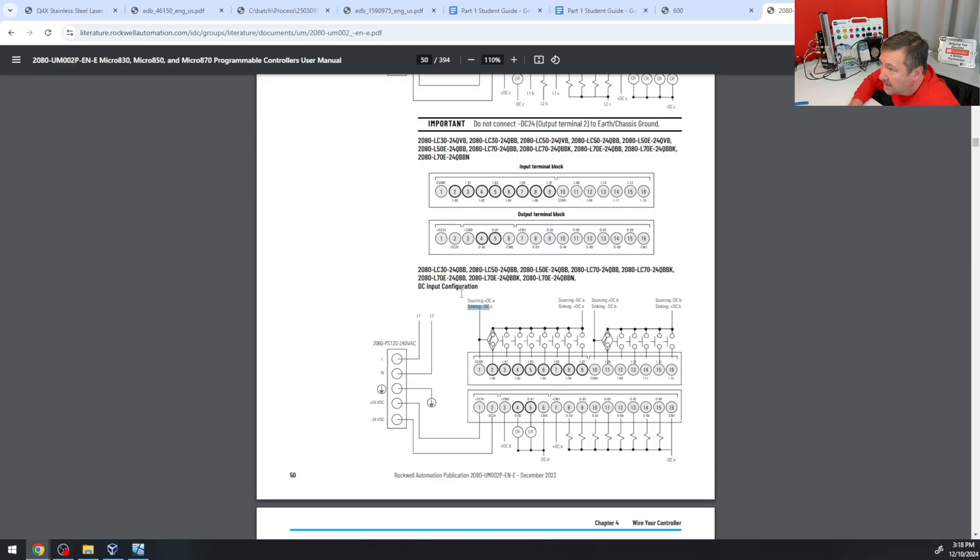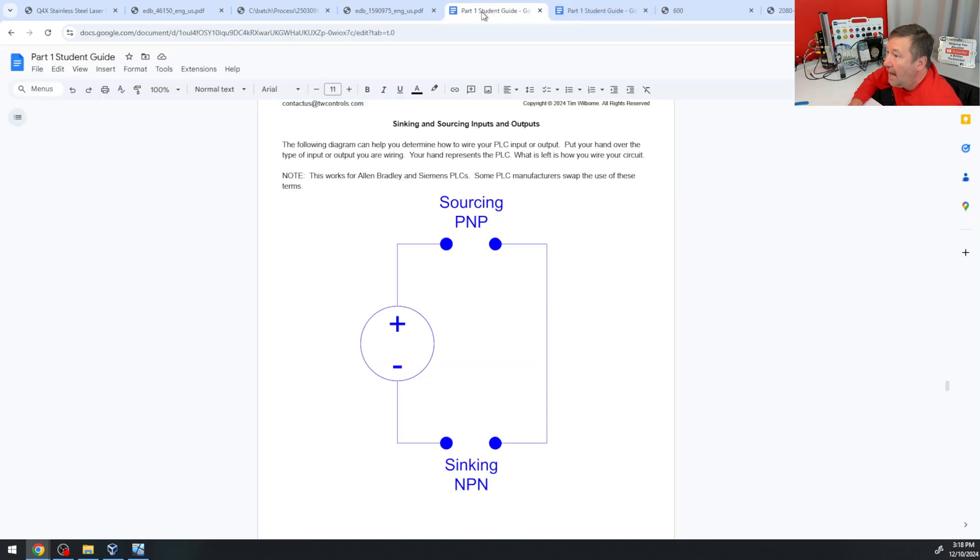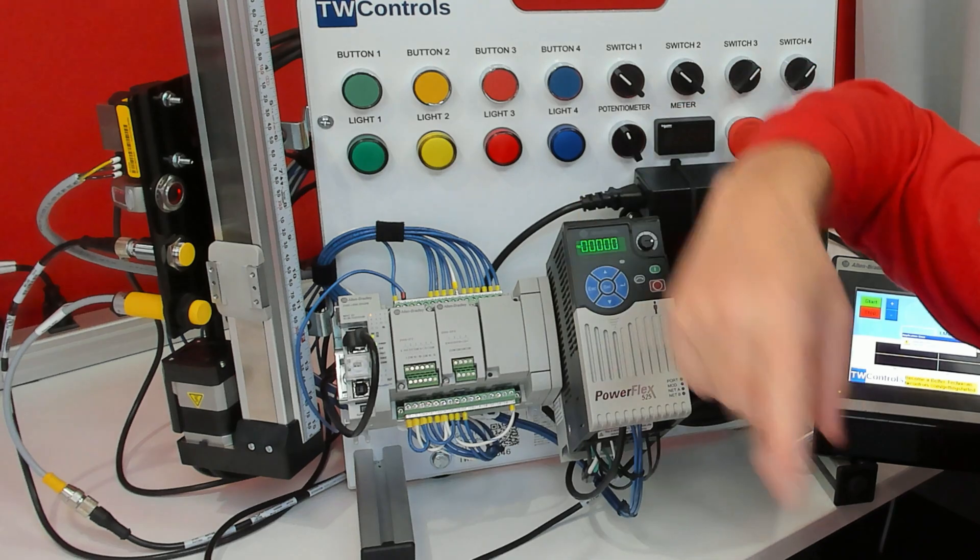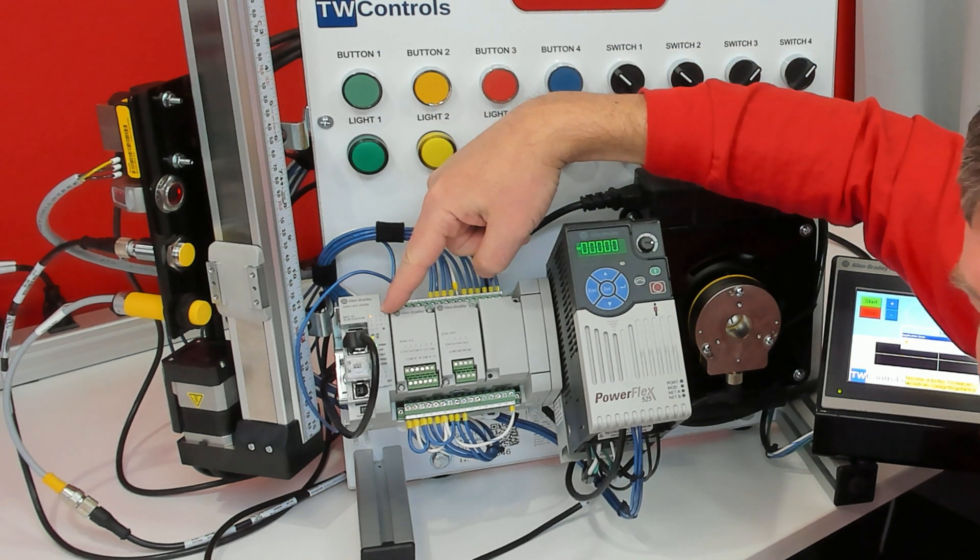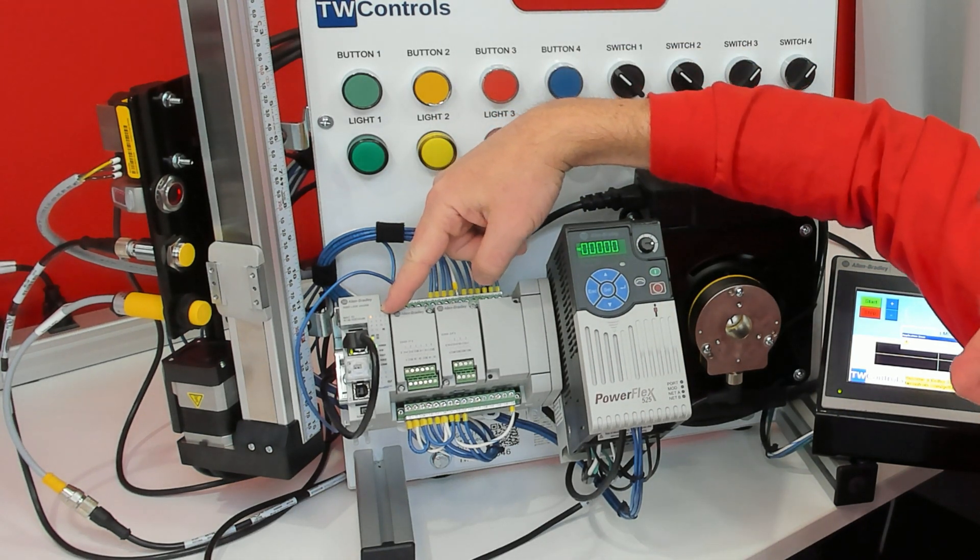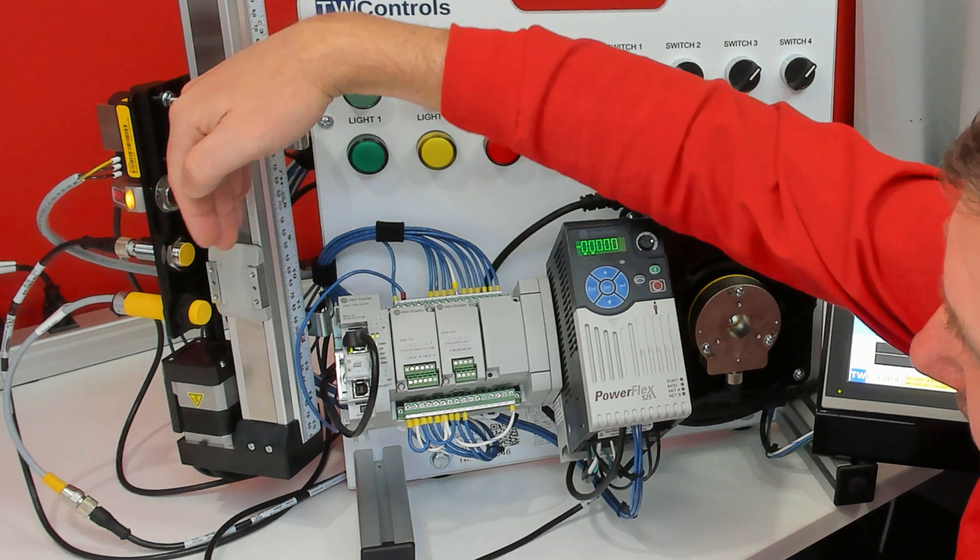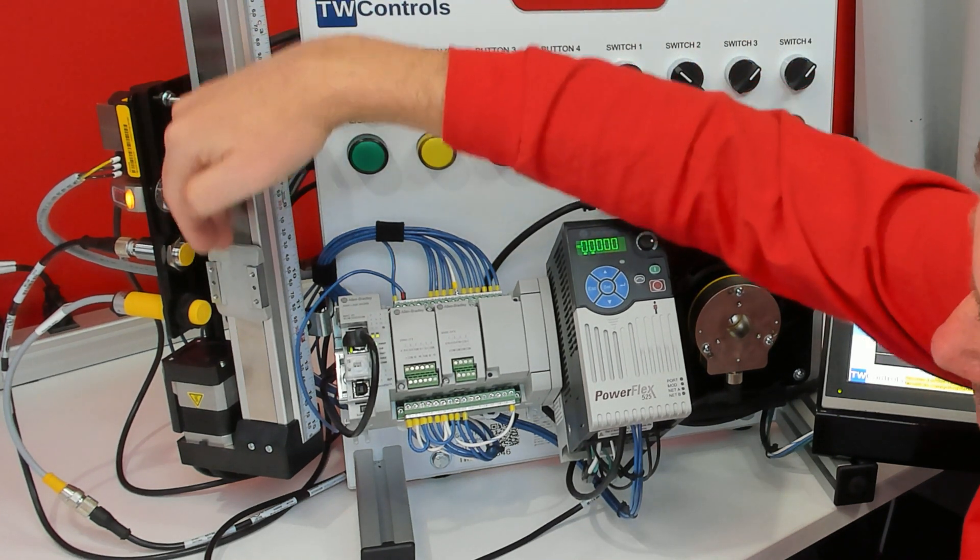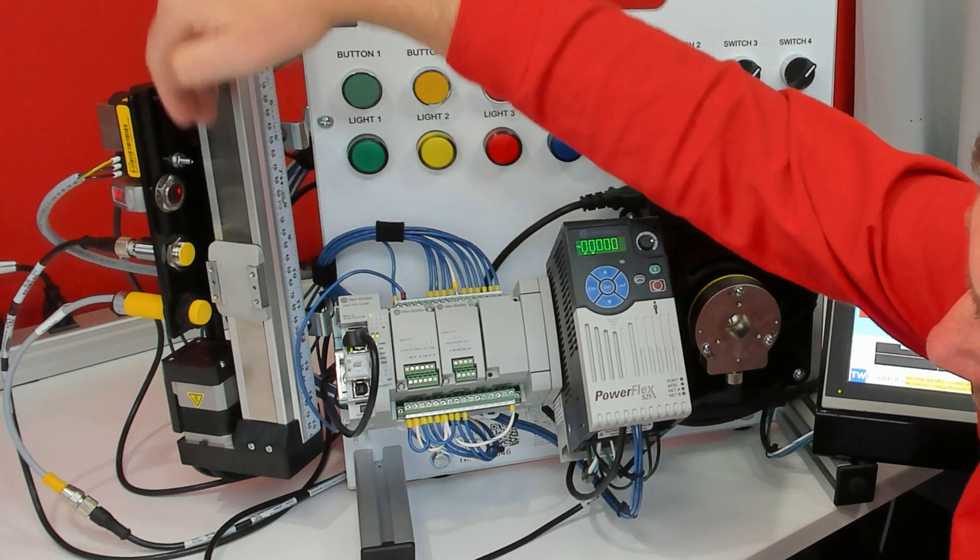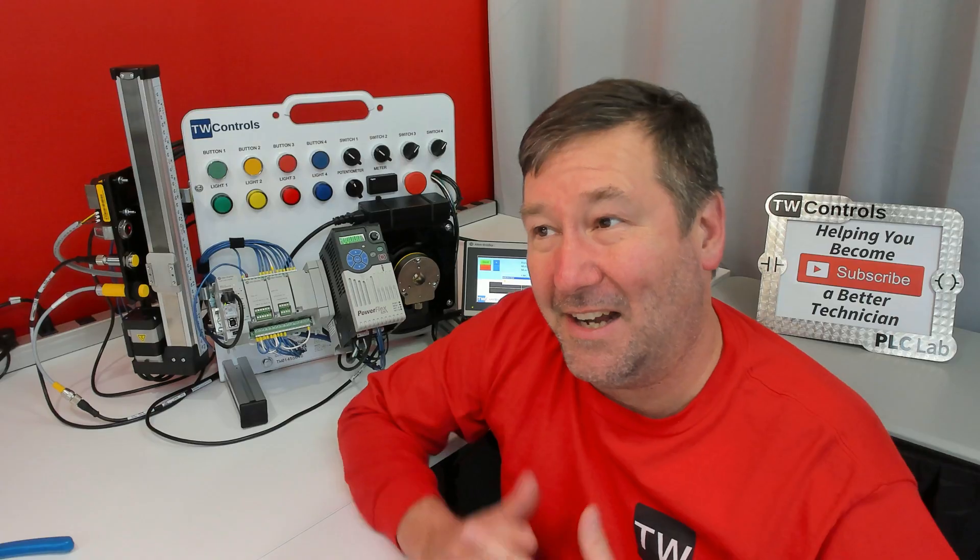And since we put plus on it, that is going to make us sourcing. And if we have a sourcing PLC input, we would need an NPN sensor. And now, it kind of makes it look like a normally closed prox, but if we put our hand over, it turns off. So now we are switching this as an NPN sensor.